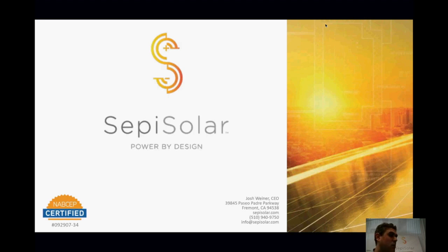And then, sort of like a car, you might have minor and major services. Minor services on an annual basis might just be swapping a filter out on an inverter if you're in a dusty environment, or spot checking the HVAC, whether remotely or on-site — costs vary depending on the data acquisition and management involved. Then you'll have more major service, like replacing the air conditioner after a certain amount of time. Those things wear out or get less efficient to the point where they're not economical anymore.